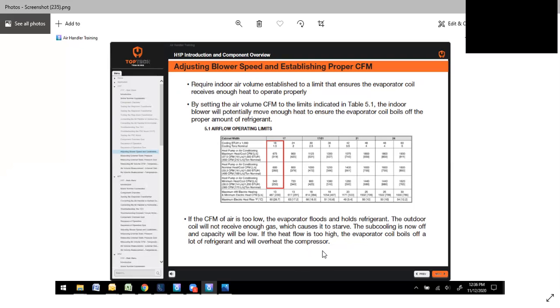The outdoor coil will not receive enough gas, which causes it to starve. The subcooling is now off and capacity will be low. If the heat flow is too high, the evaporator coil boils off a lot of refrigerant and will overheat the compressor. So it is important.